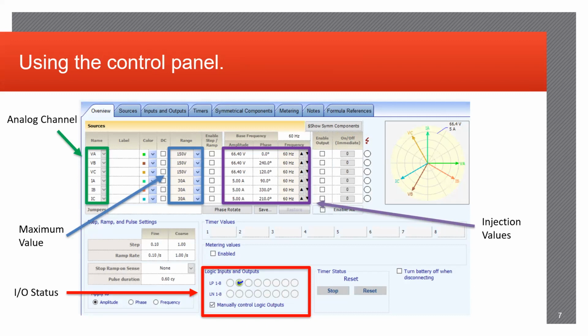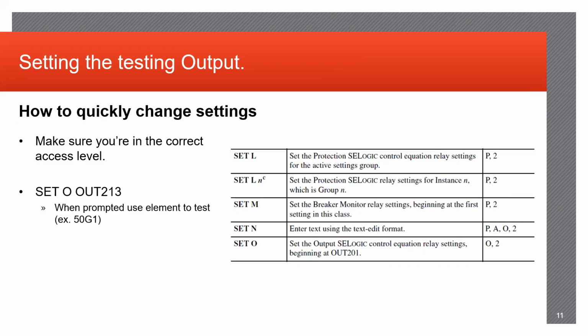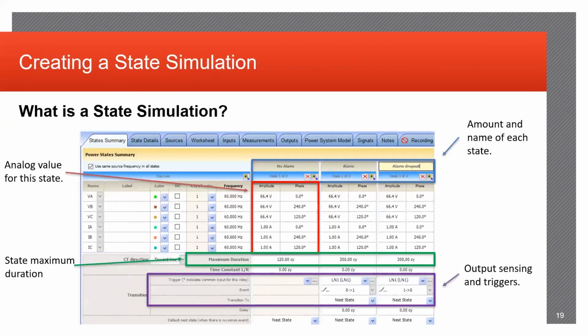Can those testing devices input a small amount of fault current? Yep, absolutely. That's usually what you'll be doing for your state sims. When you're setting up your fault current values, say you want to do an A to ground fault. In that case, you'll have your nominal voltages and nominal currents for your first state. Your second state, for an A to ground fault, you'll put something within the relay's parameters, for example 10 amps on phase A and 0.1 on phase B and C, as well as a very low voltage value, such as 5 to 10 volts on phase A, and either nominal or a little bit higher voltages on phase B and C.